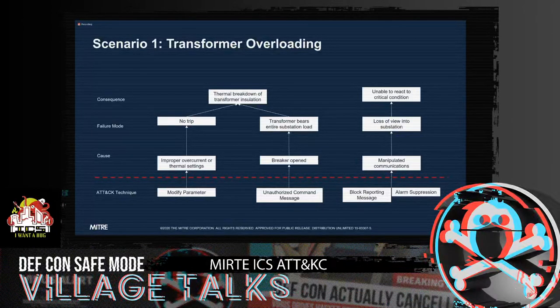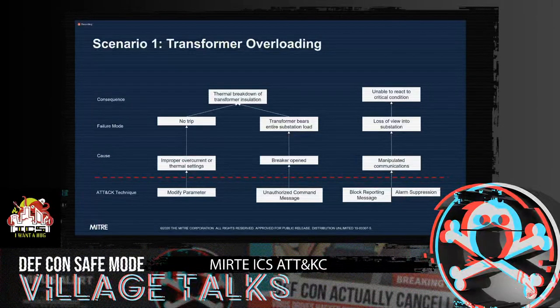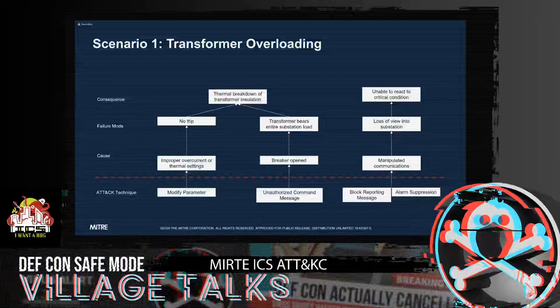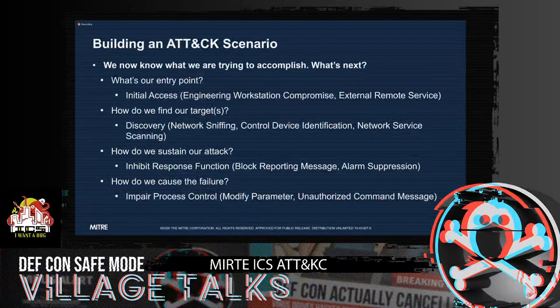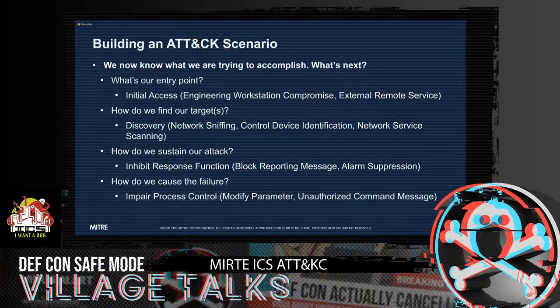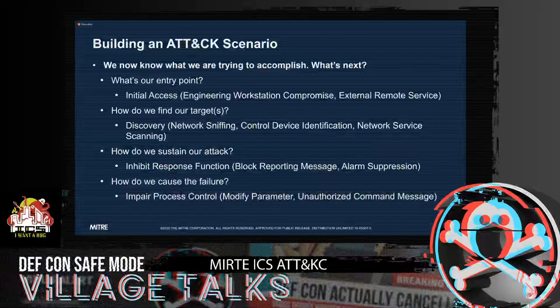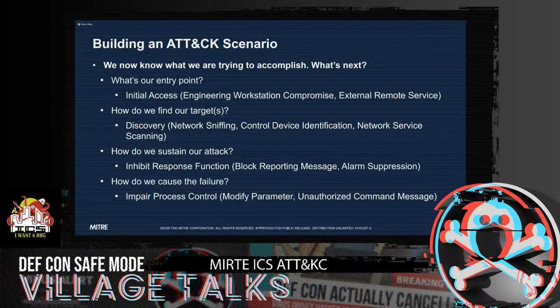We also have to consider how we sustain this attack — what do we need to do to make sure it continues so we get our ultimate consequence? We want to make the operator unable to react to the critical condition. One way is causing a loss of view into the substation by manipulating communications. The attack techniques we can use here are block reporting message and alarm suppression. Now we know what we want to accomplish — we're not just fiddling around in a testbed with no ultimate goal. So what's next? We can build our attack scenario: what's our entry point, how do we find our targets, how do we sustain our attack, and how do we cause a failure?